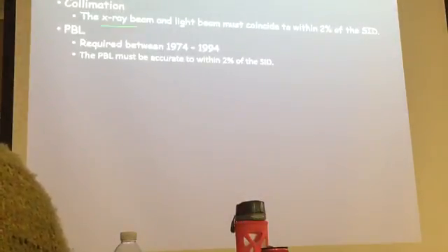Oh, I was doing some testing because our tube is off a little bit. There is a copper plate, and it has a ruler one way and a ruler this way, so you expose that and then you can see. It's really easy doing it that way, and then you can measure how many millimeters.